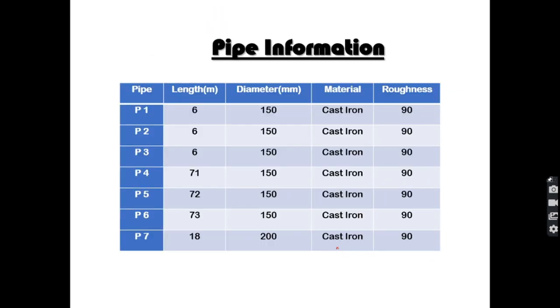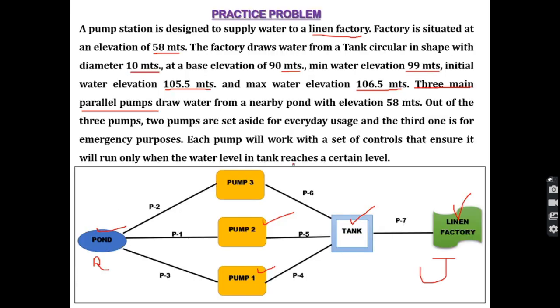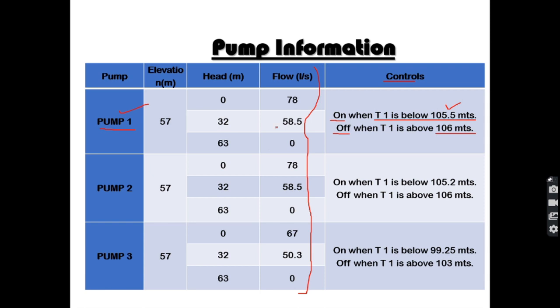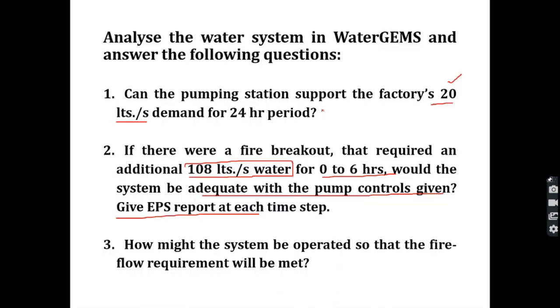The approach will be: first model the network in WaterGEMS with all the pipe information, tank elevations, pump elevations, and control conditions. Then analyze step by step — first for a fixed demand of 20 liters per second, then create an additional demand of 108 liters per second for 6 hours, check whether the system is adequate, and if not, suggest a solution.